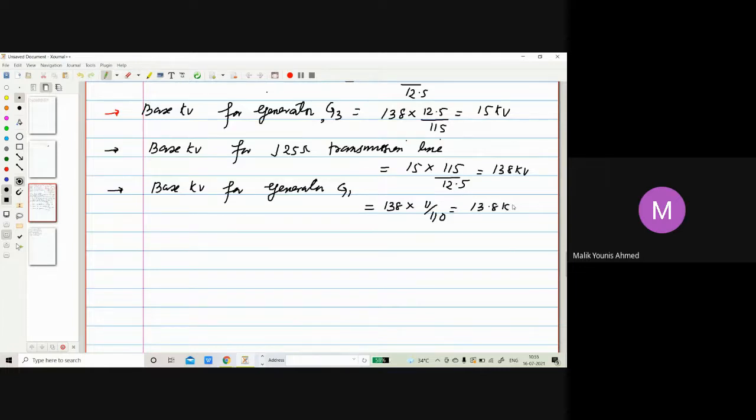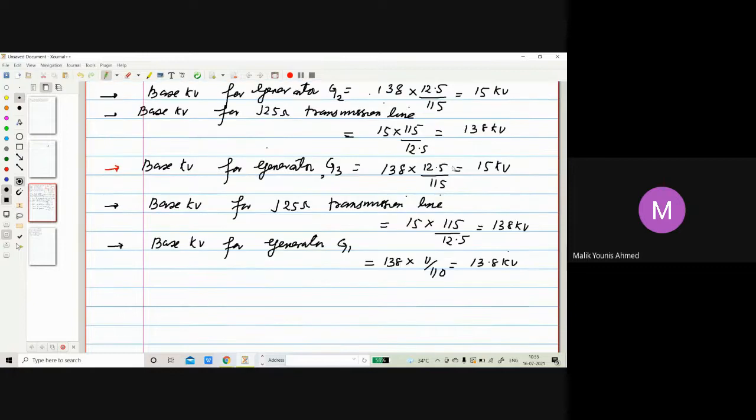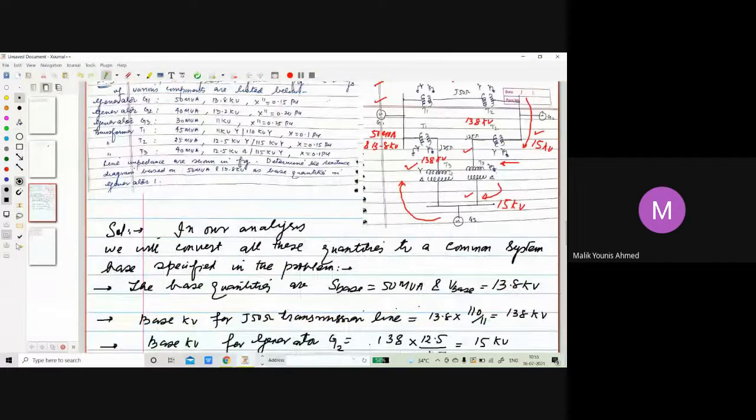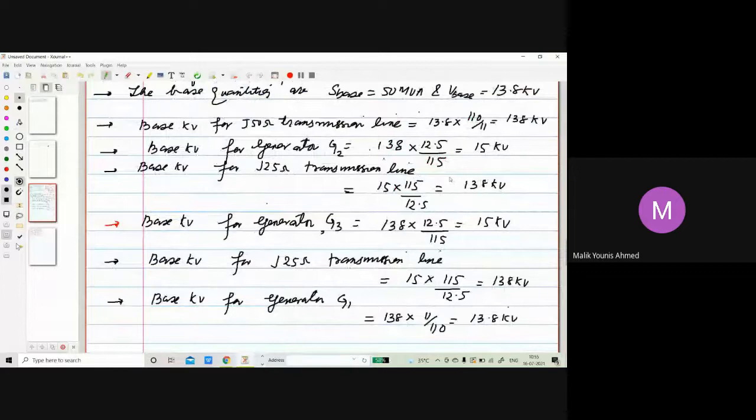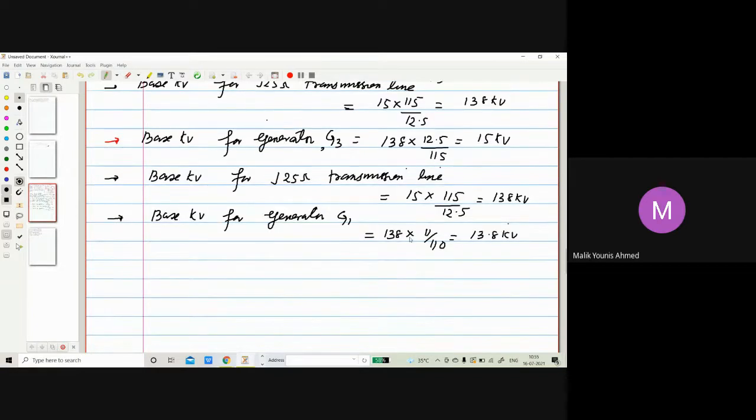That means whatever calculations you are making in the complete loop of this type of problem, those calculations are correct. So the same fundamental logic will be there, that the voltages should match, the base kV should match with the transformation ratio. It's not that you have a base kV of 138 and you can write a transformation ratio of secondary by primary as 13. No, whatever ratio you make, that primary side should be approximately equal to the base kV. That's the fundamental. Okay.